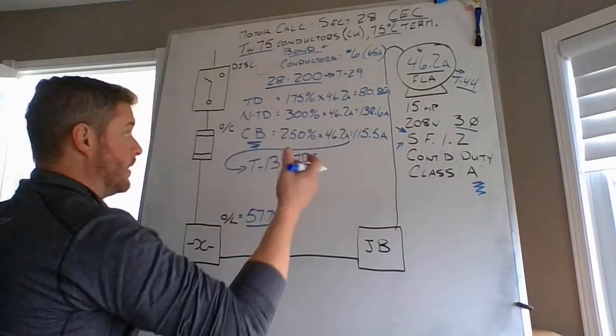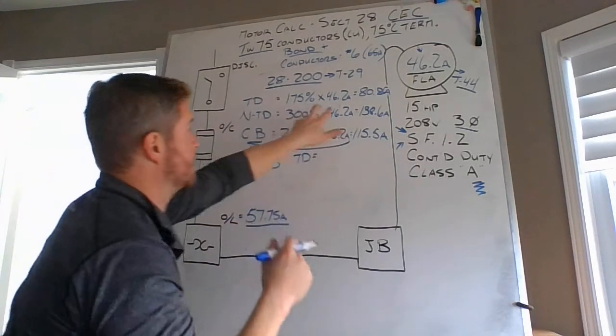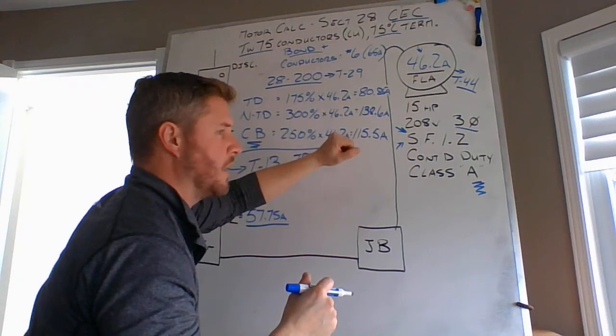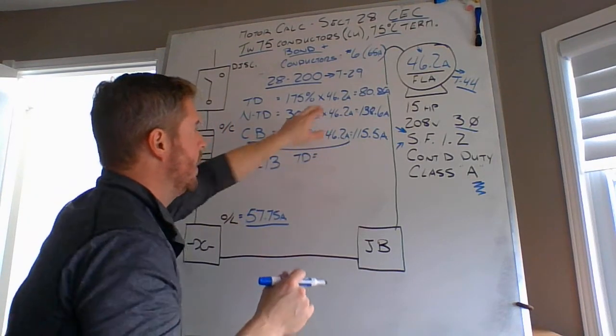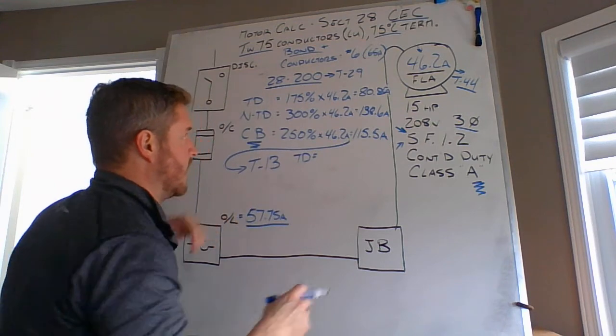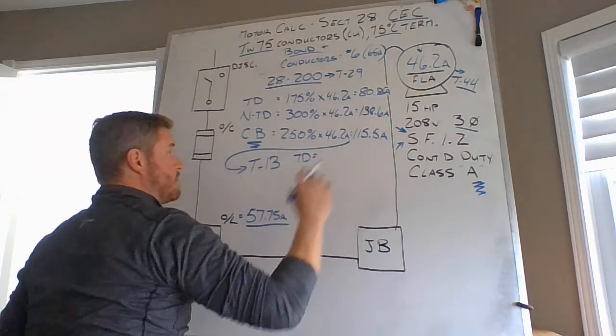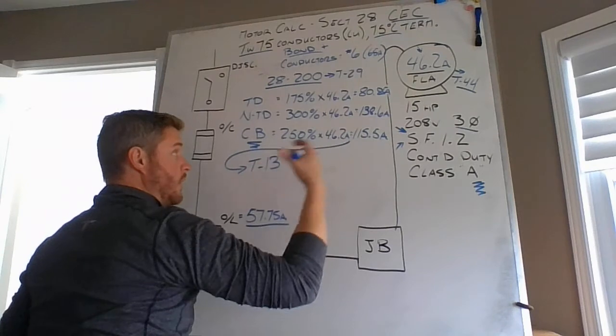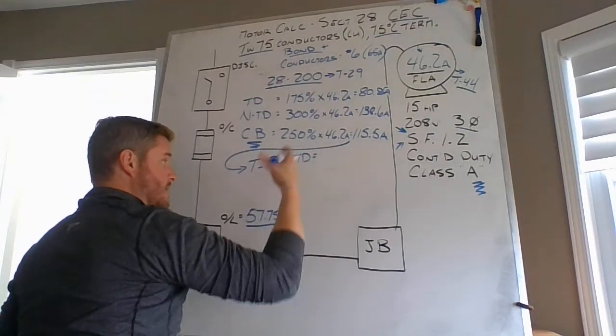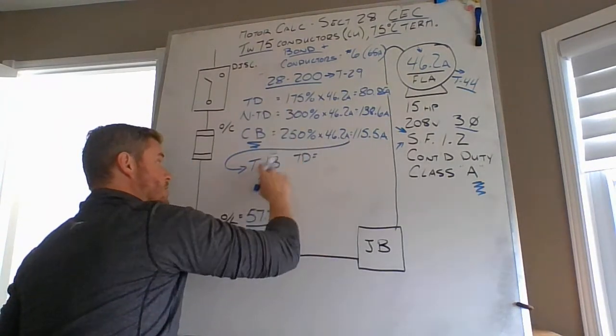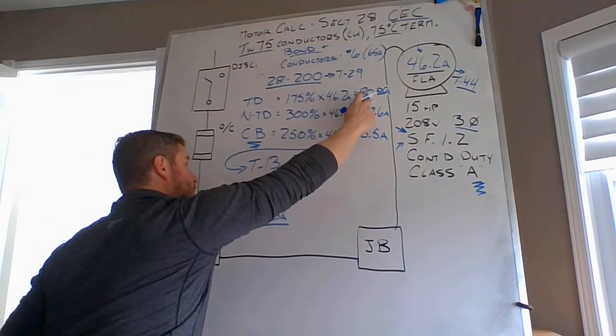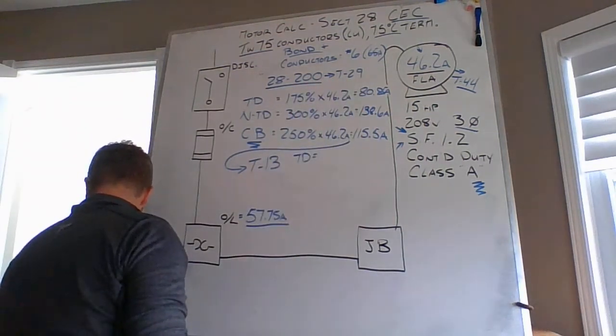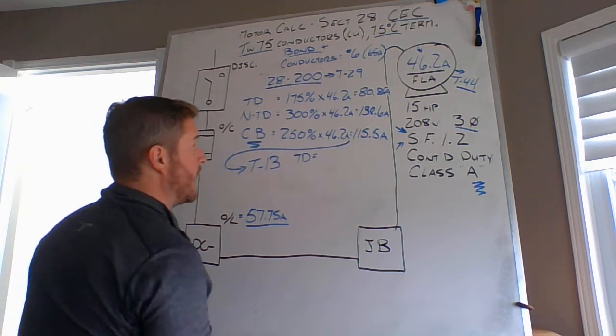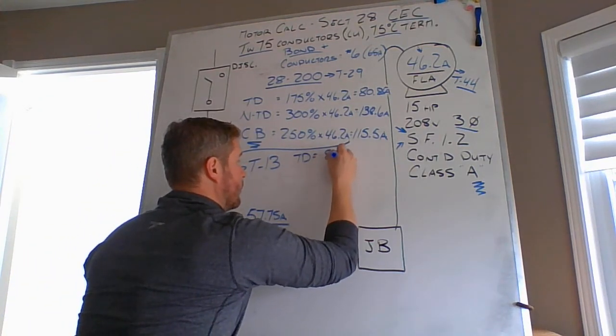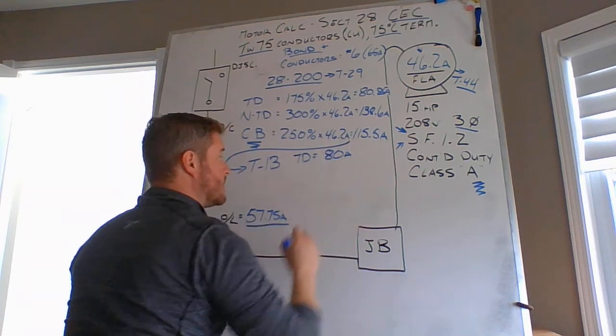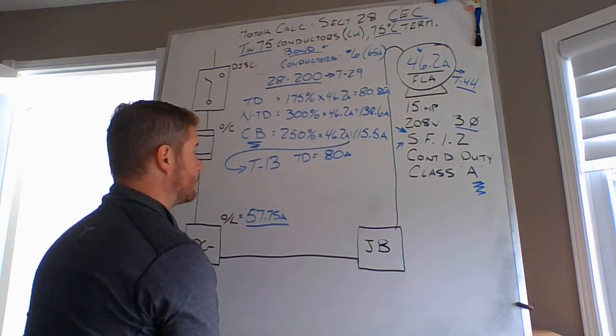So I'm looking at that time delay fuse being 175%. I switched those two numbers. I used 42.6. That was the wrong thing to do. It's actually 46.2. My mistake. 80.85 amps is my maximum calculated value for the installed fuse size for this time delay fuse. I go to Table 13 for my time delay fuse having a maximum value of 80.85. I should be able to get away with an 80 amp fuse installed for a time delay.